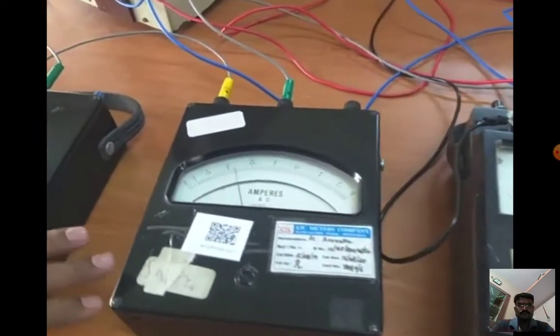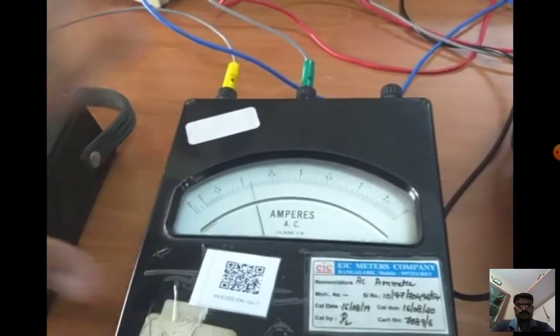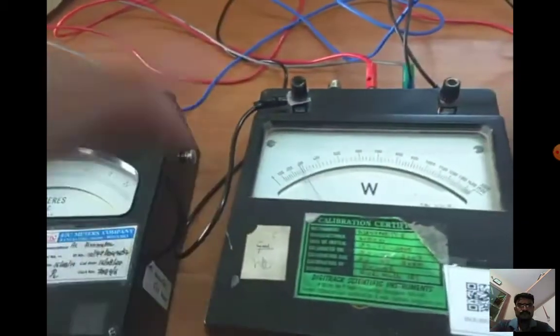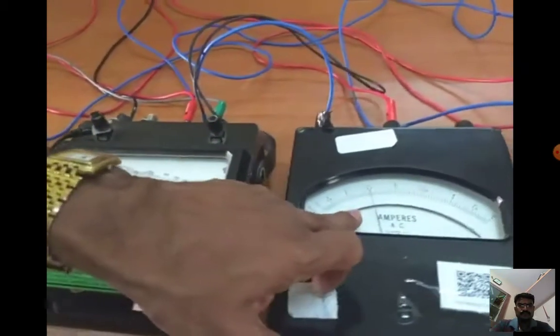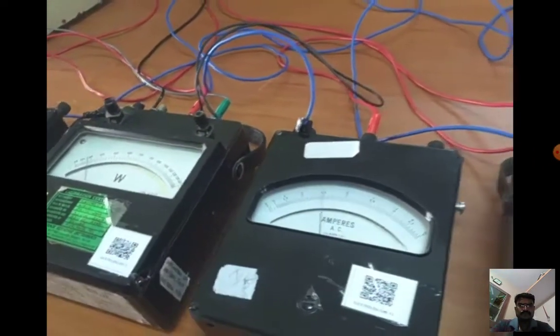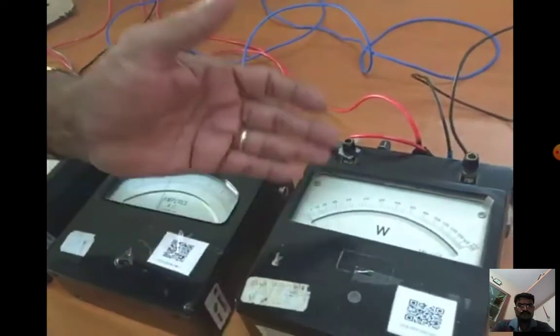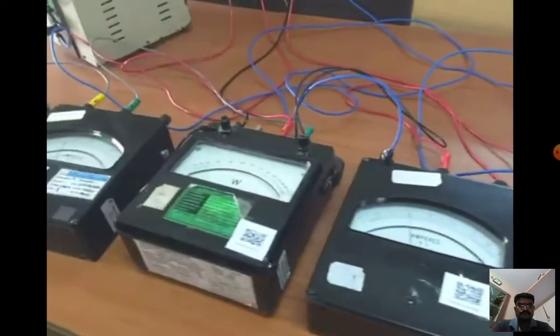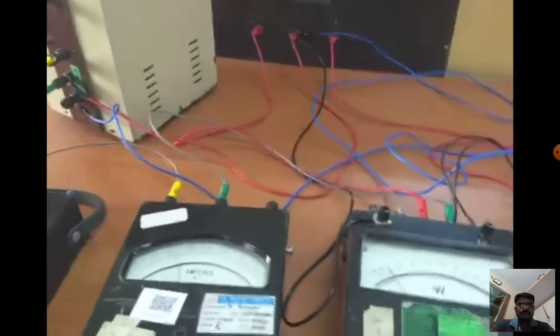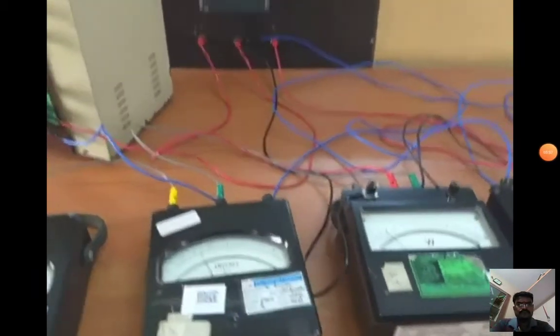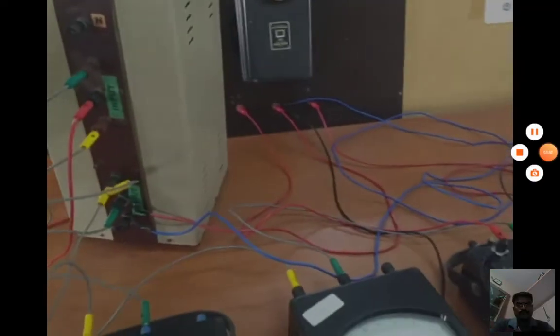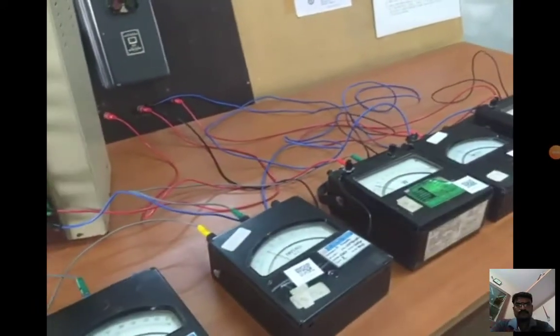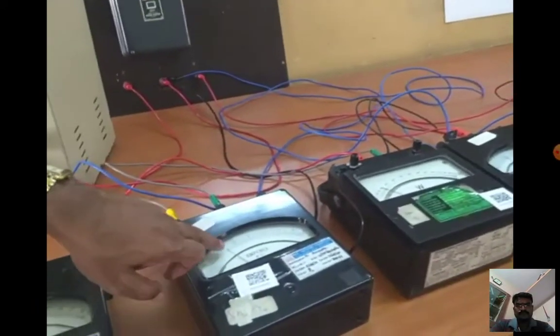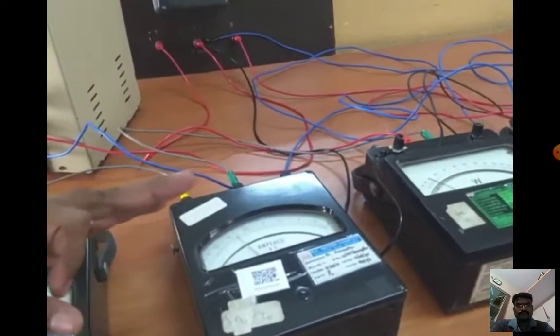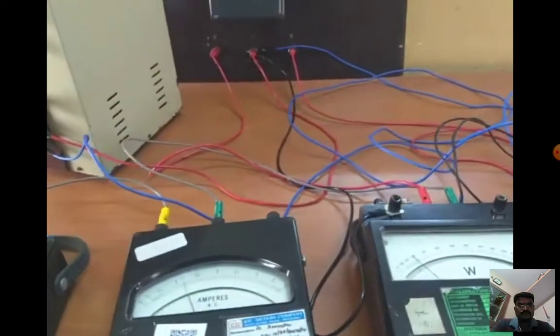The corresponding ammeter A1 value we should take, the wattmeter W1 value we should take, and the ammeter A2 value and W2 wattmeter values we should take for the no load test. Once we complete this one, what we should do? We should increase the current up to 8.2 amps. That's the rated current for the blocked rotor test.